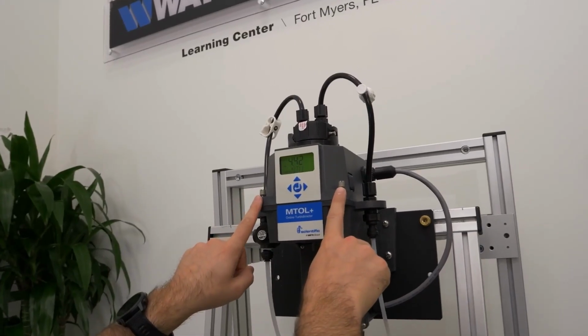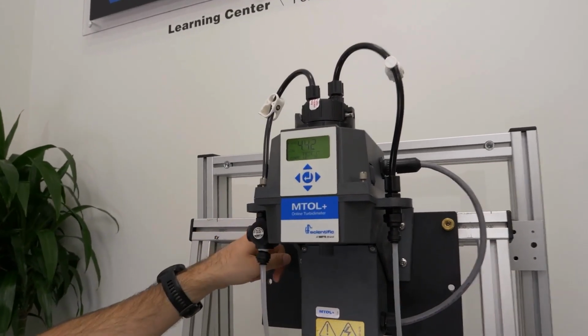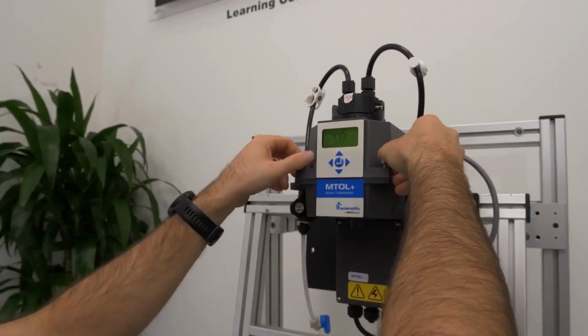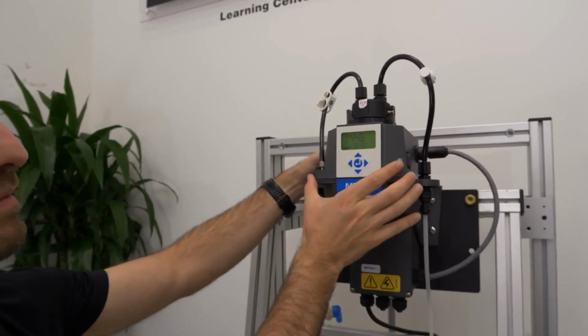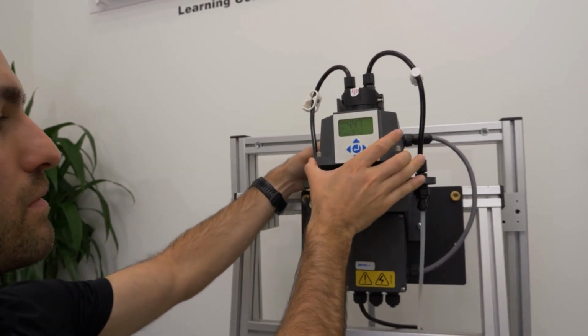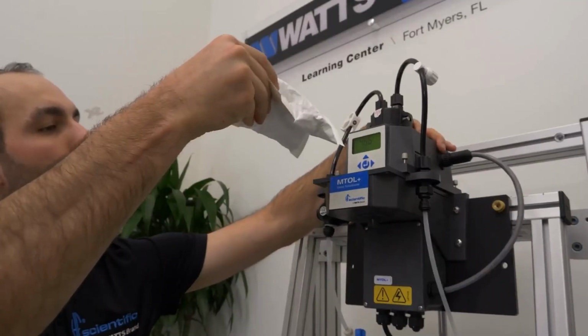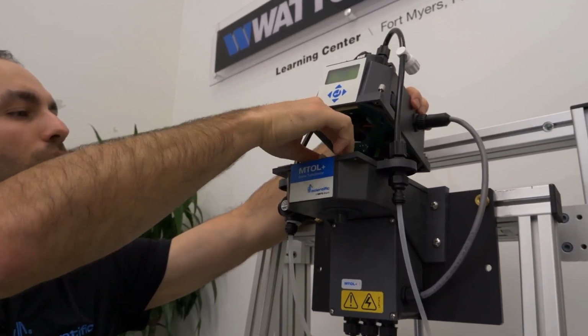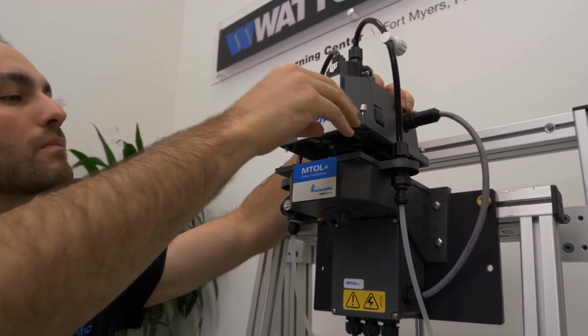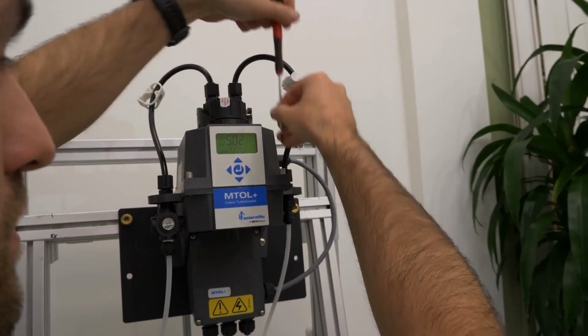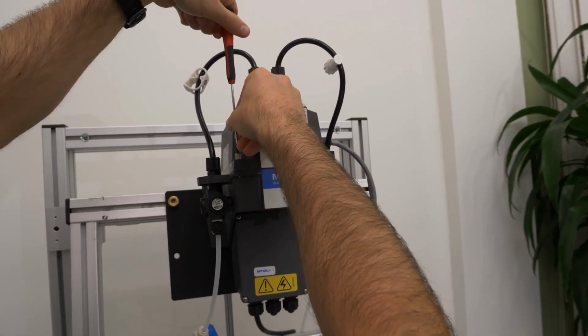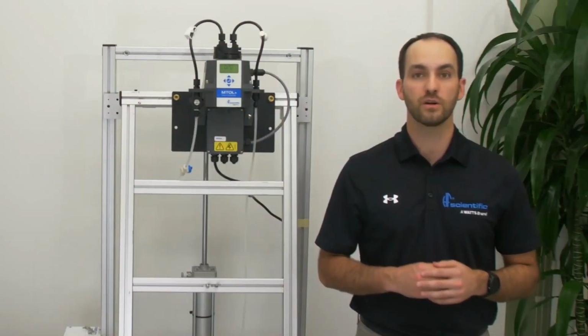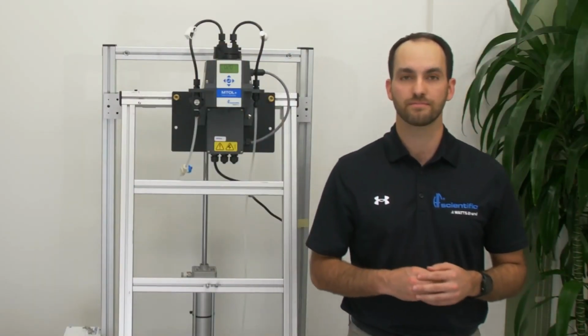There are 4 thumb screws which hold the casing of the electronic service module together. Loosen these screws so the housing comes apart. Remove the desiccant from its pack and place it inside the ESM. Personally, I like to tent the desiccant so that all surface area is exposed to the internal air and move it to the front of the enclosure so it doesn't block the fan.